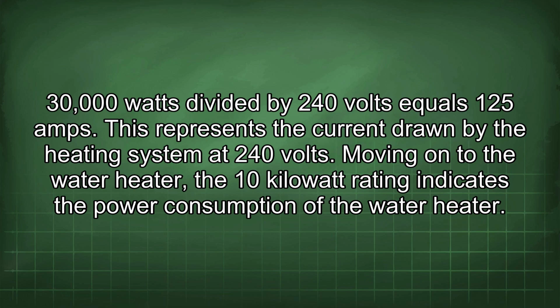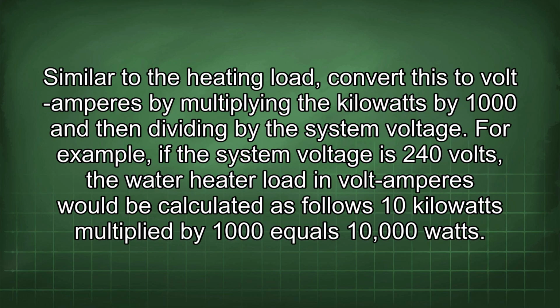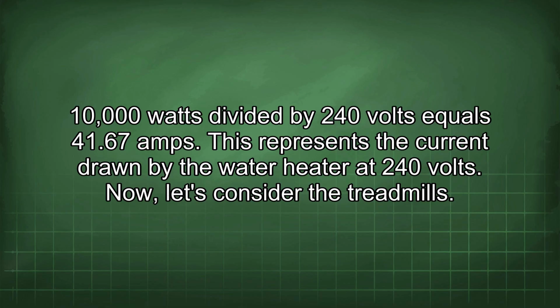Moving on to the water heater, the 10 kilowatt rating indicates the power consumption of the water heater. Similar to the heating load, convert this to volt-amperes by multiplying the kilowatts by 1000 and then dividing by the system voltage. For example, if the system voltage is 240 volts, the water heater load would be calculated as follows: 10 kilowatts multiplied by 1000 equals 10,000 watts. 10,000 watts divided by 240 volts equals 41.67 amps. This represents the current drawn by the water heater at 240 volts.